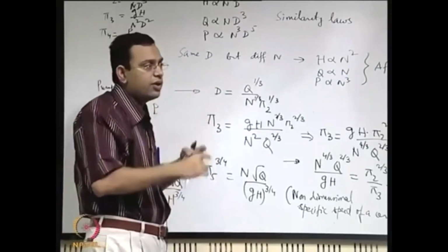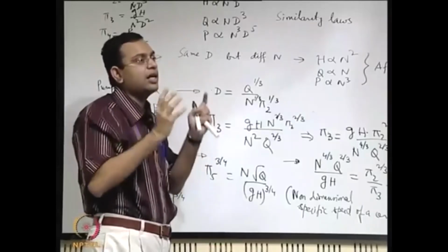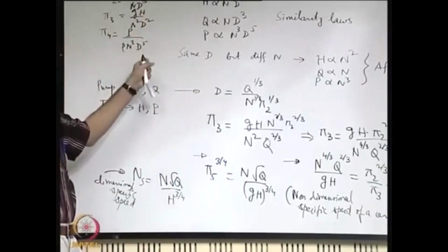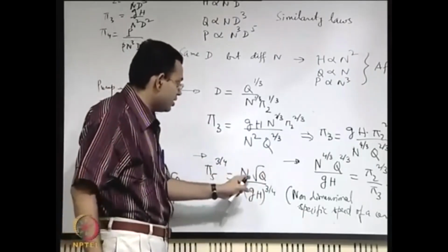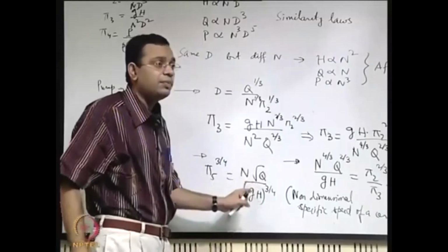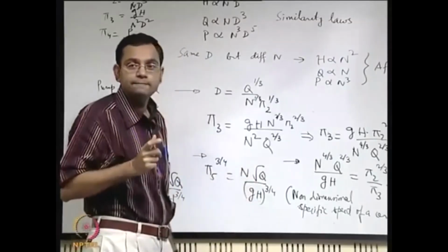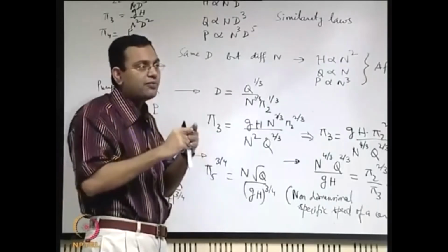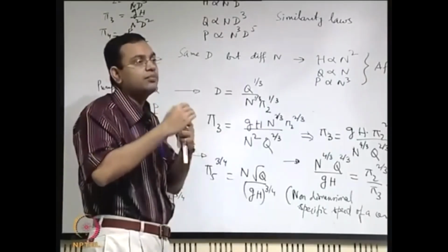But say you have an axial flow pump. For the axial flow pump the geometry is a bit different, the flow nature is a bit different, but these are the important non-dimensional parameters which are still valid for that. For that type of situation you have this characterization independent of the rotor geometry, and therefore even if it is not geometrically similar you can have a comparison between pumps of different types.